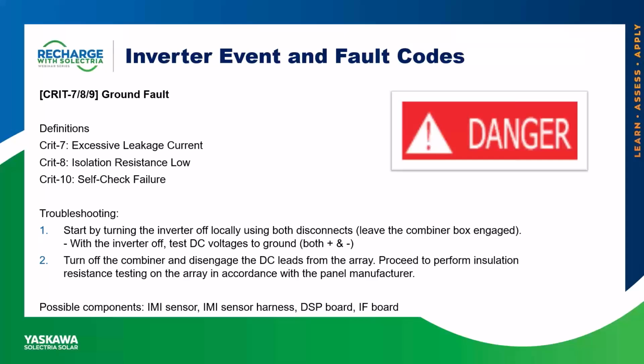The primary component inside of non-DCG XGI 1500 inverters that detects ground faults is the IMI sensor. The IMI sensor is a CT that wraps around the positive and negative DC conductors within the interior of the inverter, and the sensor itself is looking for a delta in current of essentially 0.